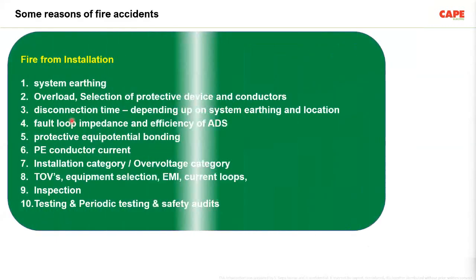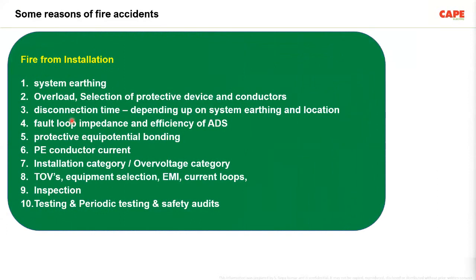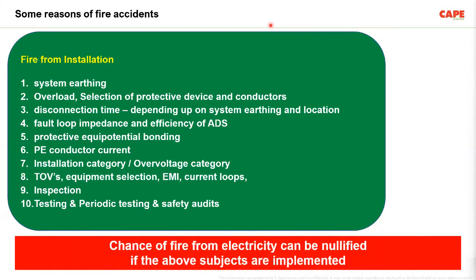So the 10 points which I wanted to highlight, the important points which need to be implemented in an electrical installation, are: number 1, system earthing; number 2, overload protection and selection of protective conductors and devices; number 3, disconnection time. Depending upon the system, you should implement the disconnection time, fault loop impedance and efficiency of automatic disconnection, protective equipotential bonding, PE conductor current, installation category or over voltage category, temporary over voltages and the EMI current loops, inspection and testing. These are the 10 important points which I felt, if we do them properly, can actually reduce the number of electrical accidents very much in an electrical installation.